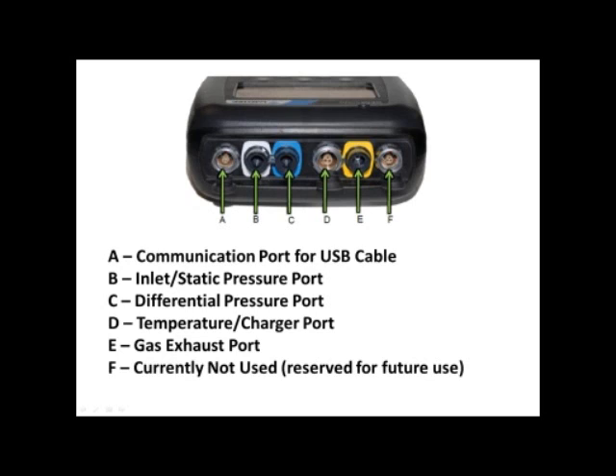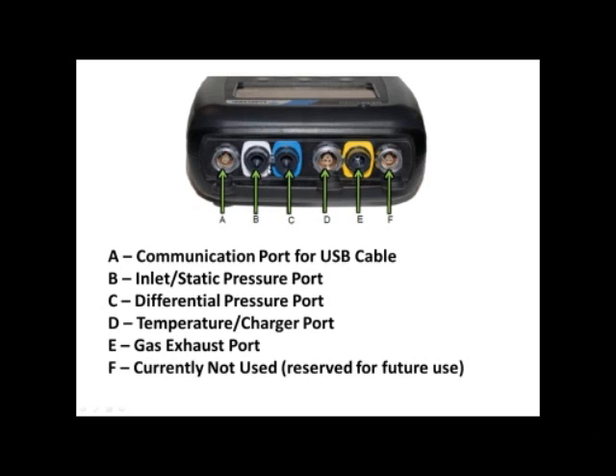As you can see in this image, I'm just going to go over the two main ports that we're going to be using for the field calibration purpose. Starting with the white port indicated by the letter B, which is the inlet and static pressure port. This is the port we're going to use to connect the gas, for the gas to go into the unit. The next port is the yellow port, which is the exhaust port, indicated by the letter E on this image. So these are the two main ports we're going to use for the calibration purpose.